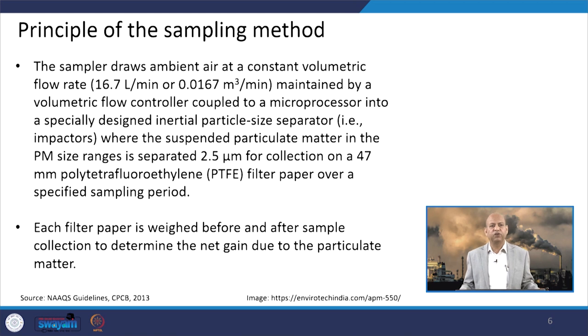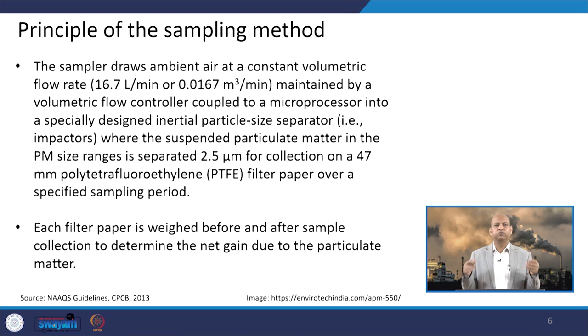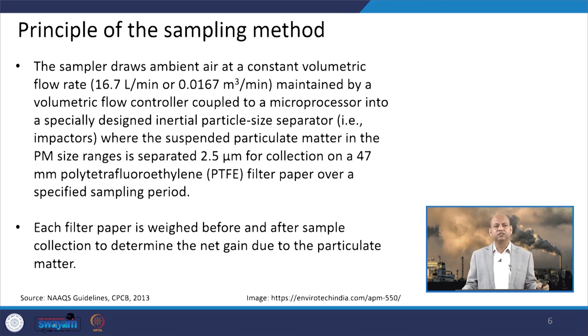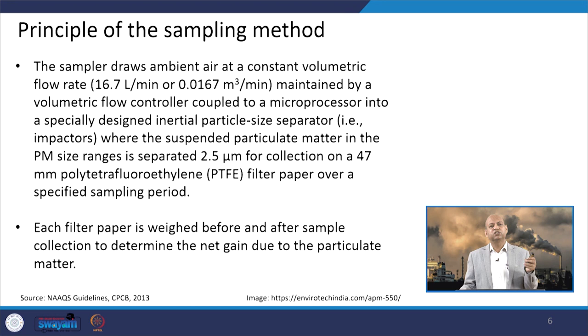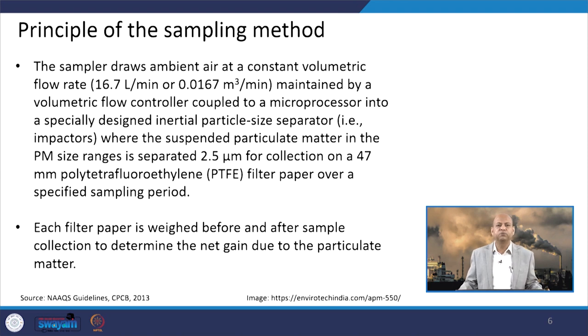The principle behind sampling of PM 2.5 is that it draws ambient air at a constant volumetric flow rate of around 16.7 liters per minute or 0.0167 cubic meters per minute, maintained by a volumetric flow controller coupled to a microprocessor, into a specially designed inertial particle size separator — also known as an impactor — where suspended particulate matter in the PM 2.5 size range is separated for collection on a 47 mm PTFE filter paper over a specified sampling period.